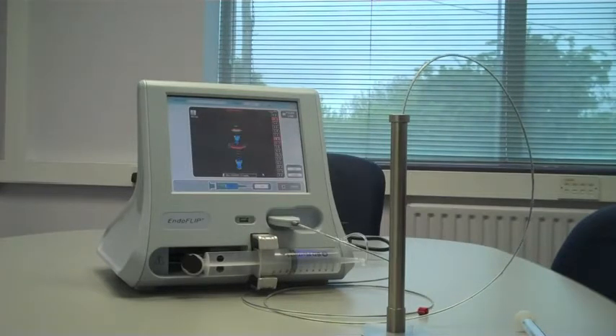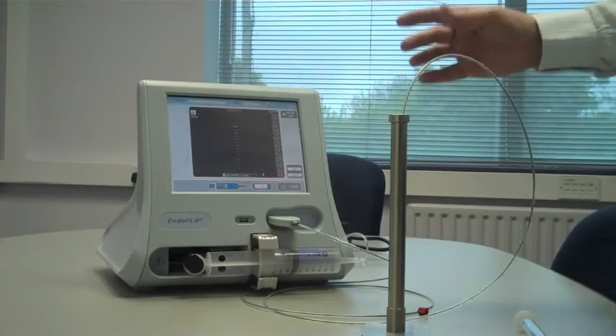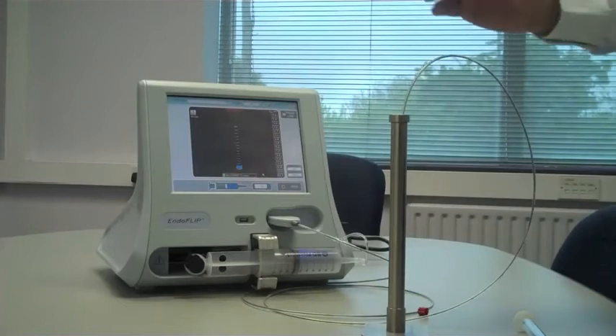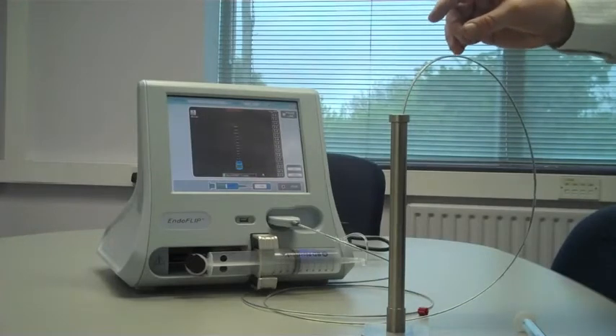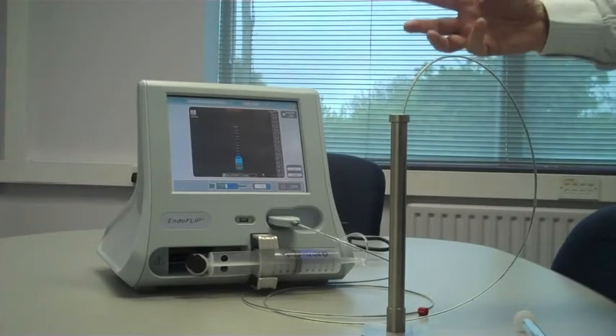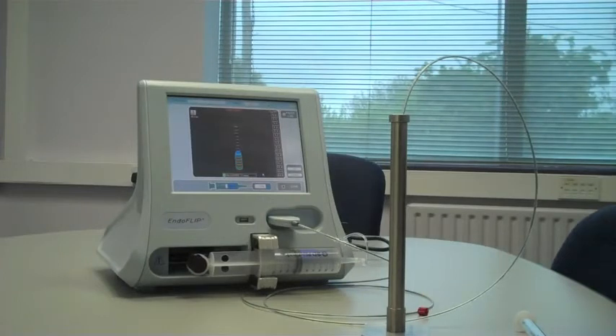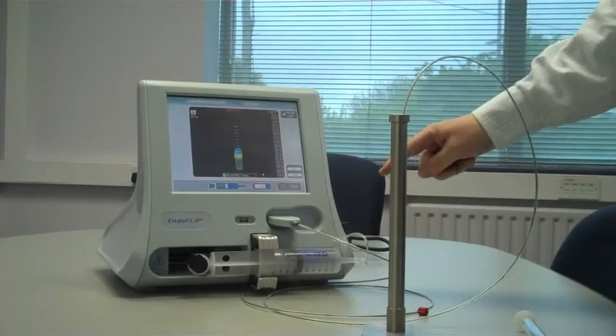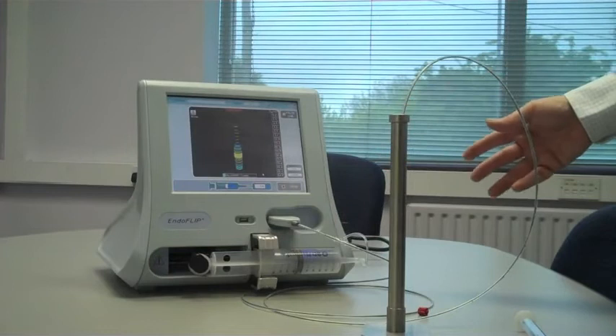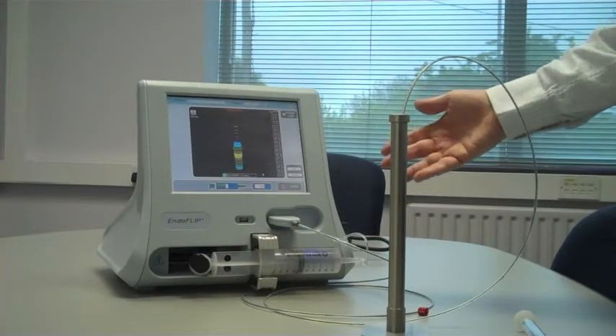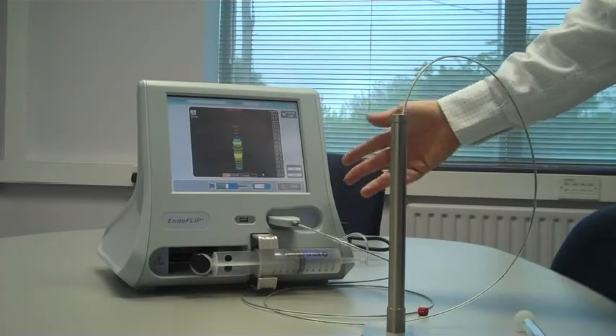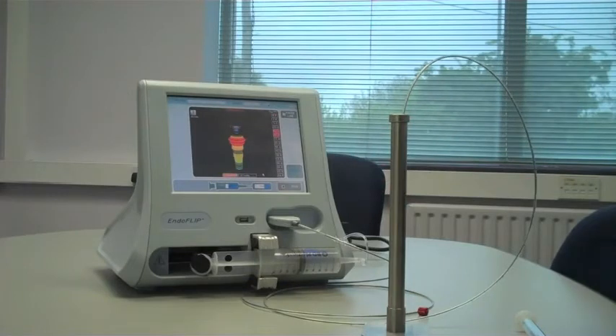So what this is doing is filling the catheter line with saline and displacing the air in the catheter with saline, so that the balloon is always filled with saline. This is a diluted saline solution here. This is not the standard saline within the hospital, and you should never just put standard saline in there. So what's happening is the catheter is filling up.